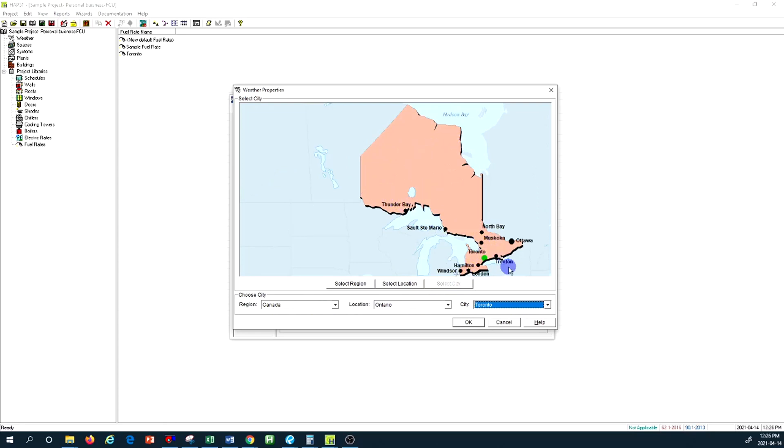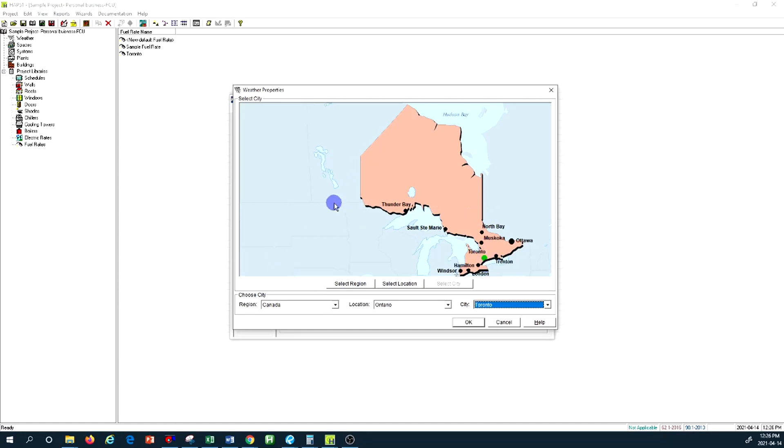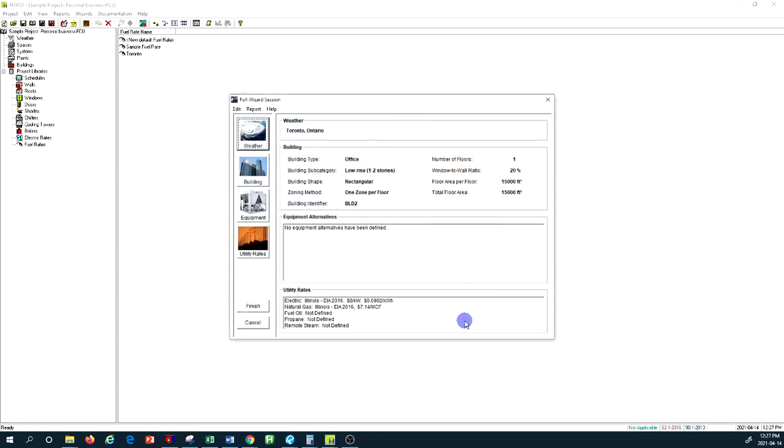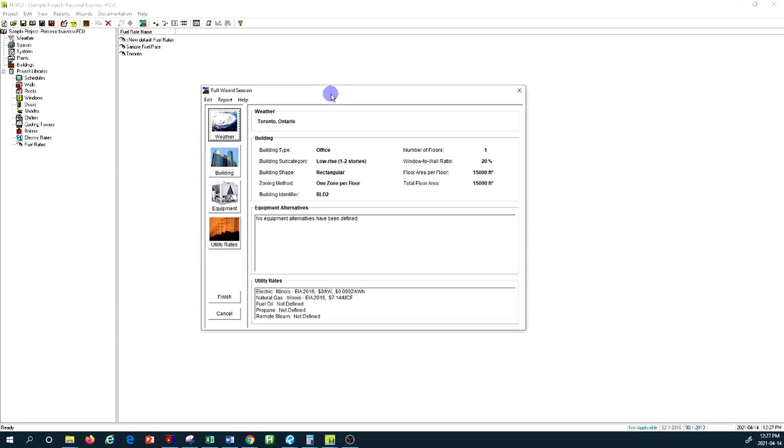Then I go to city and it shows the local area within the province of Ontario. In Carrier HAP it gives you about eight locations you can select in the province of Ontario and I've selected Toronto. This is required for all of your calculation because the elevation of your location or building location and its weather data, which Carrier HAP contains from the ASHRAE standards, would be helpful for understanding the peak load calculation for the heating degree days and cooling degree days based on worst-case scenario design conditions.